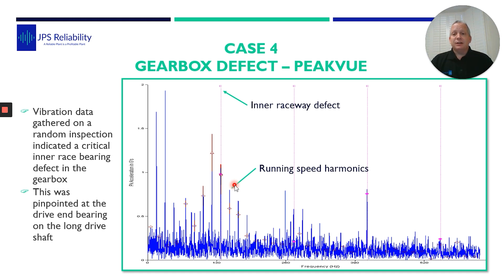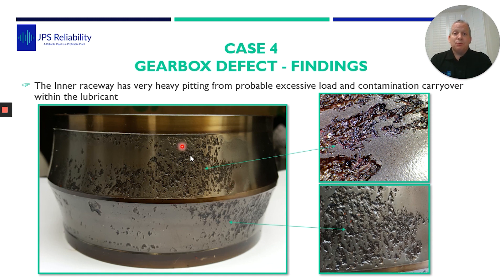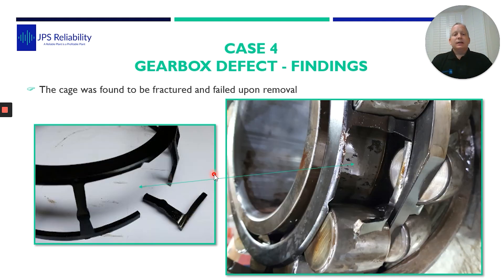The classification was very urgent — they needed to schedule the gearbox removal before short notice became a functional failure. Fortunately they did remove it before it failed. What we found on both shafts was an area of spalling. As the bearing was failing it was also being over-rolled within the lubricant. When we took it apart, we had marked all the bearings — drive end, non-drive end, top, bottom, and importantly where the weights were. It turned out that at the furthest point of the weight swing, where the highest load and shock occur, it's always the same point — the weights are bolted to the shaft and don't move — so that same point on the inner race is under the highest stress all the time. On the opposite side, where you get some carryover, you can see it's starting to damage the inner race as well.